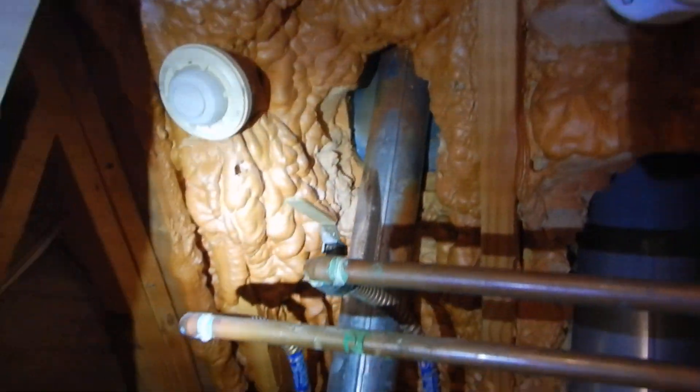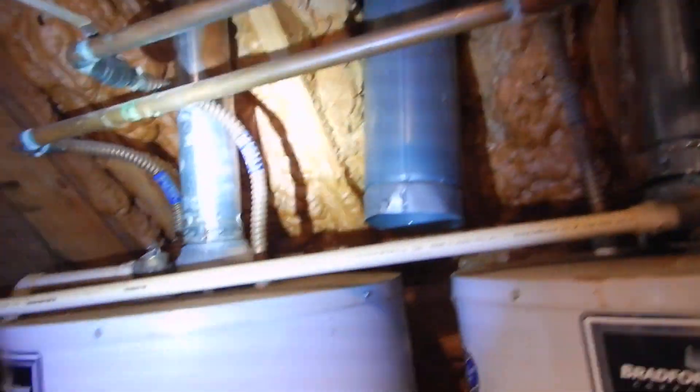Now these flues are very interesting. If you look down here in the safety pan, that's the color of the insulation. But when we come up here we get this nice brown color, even a burnt color. That's because this is all oxidizing.